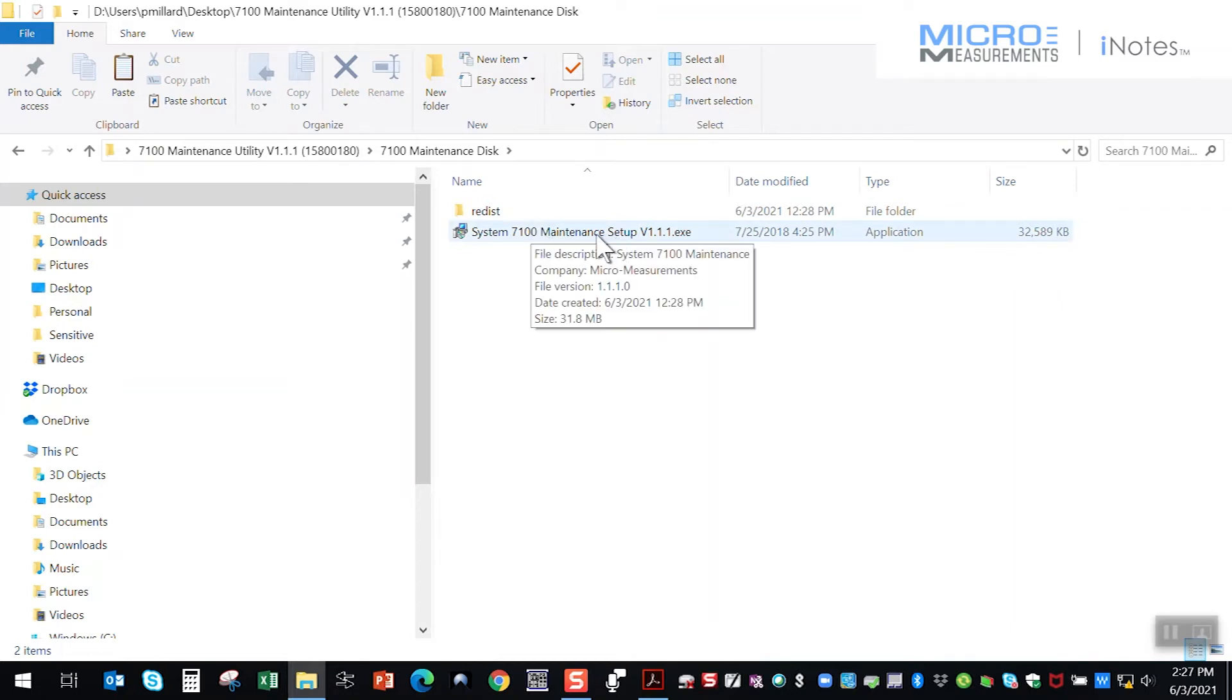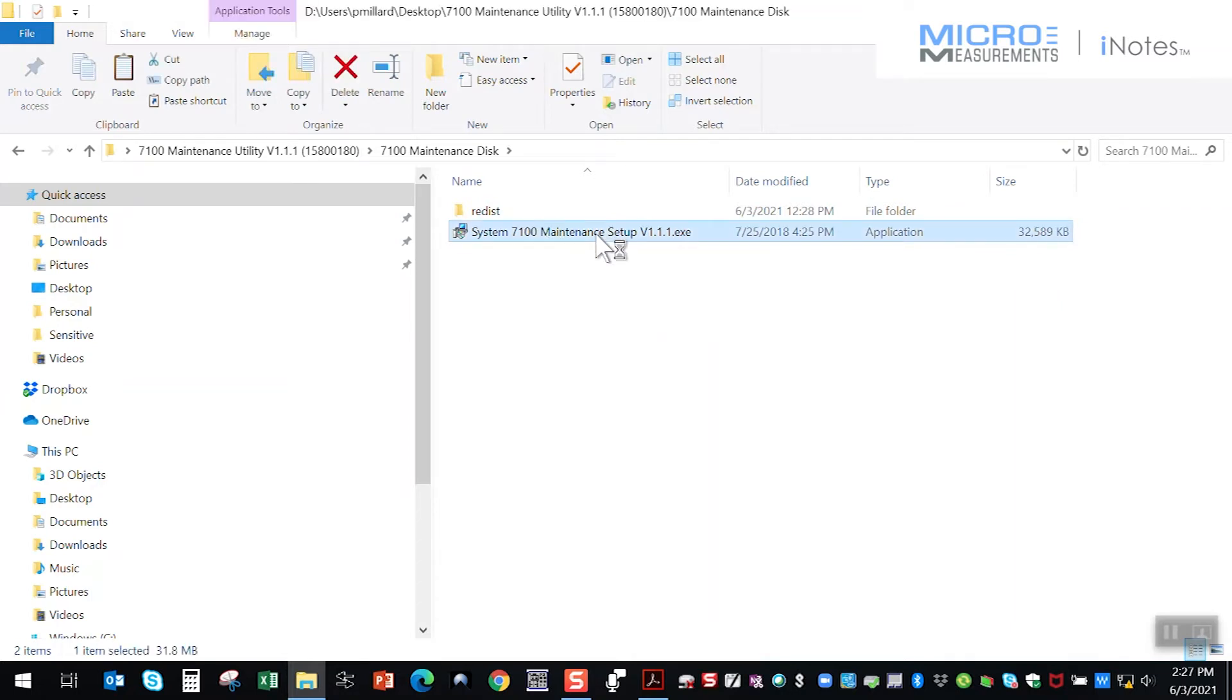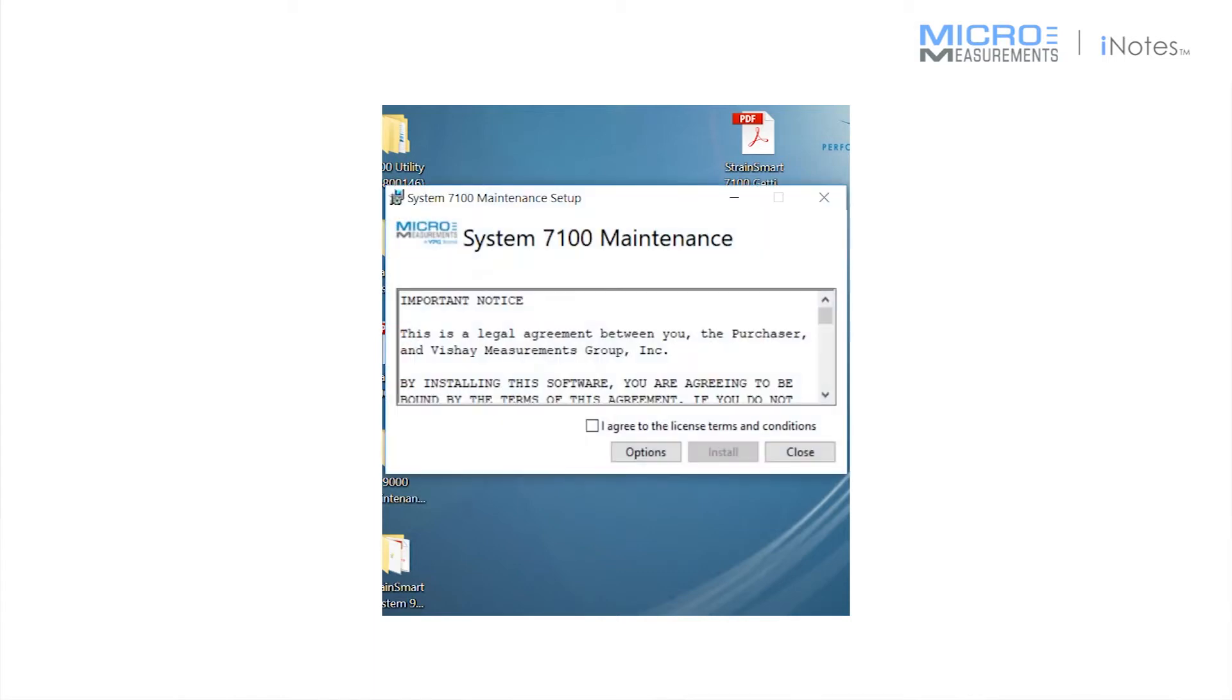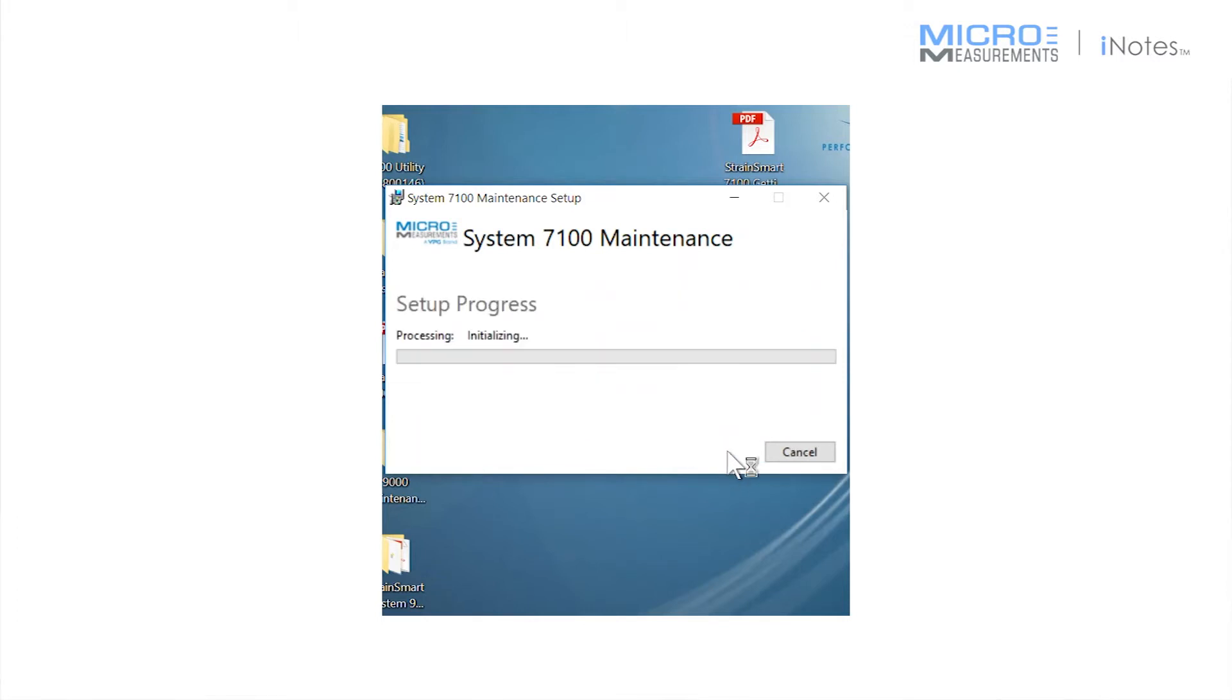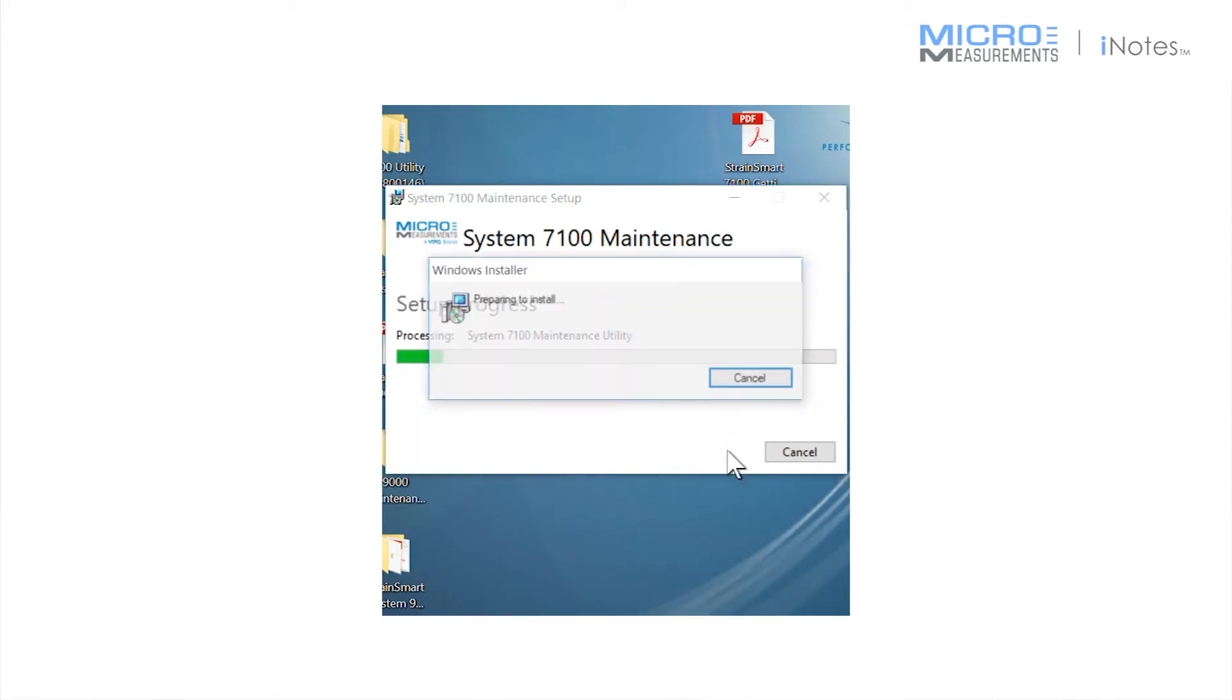But anyways, inside there is going to be an executable that you need to locate and run the maintenance utility setup. Inside that maintenance utility setup, there's going to be several beneficial things. The minimal one is going to be to assign the scanner, find the scanner and assign it so that StrainSmart knows where to look. There's going to be a couple other features that are going to be offered as well regarding the firmware on the scanner, the opportunity to upgrade it. And we're also going to spend a couple of minutes talking about how the system can perform its own calibration using what we refer to as a VCAL card, which means a voltage calibration card.